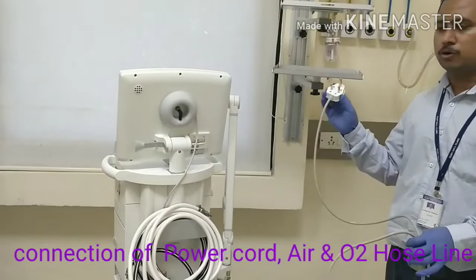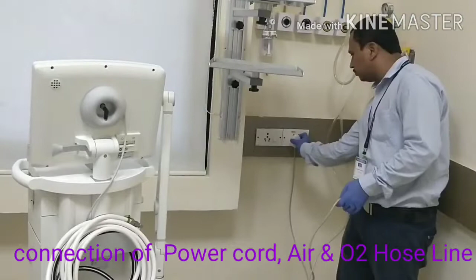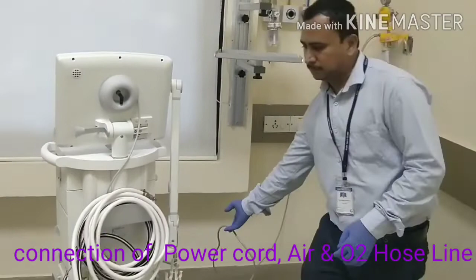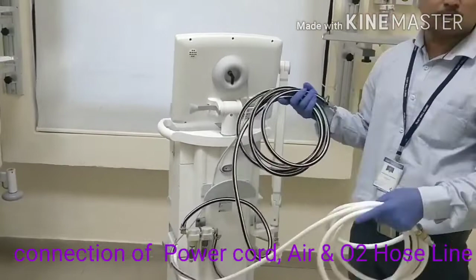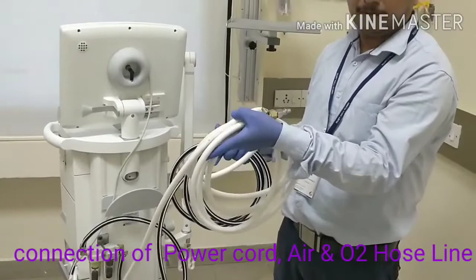This is the main power cord of the ventilator. You have to connect it at the UPS connection. This is a UPS connection and you have to plug it in. Switch on the ventilator. Next, the ventilator has two hose lines. This white hose line is for O2 supply and this black one with a white line on it is for air supply.